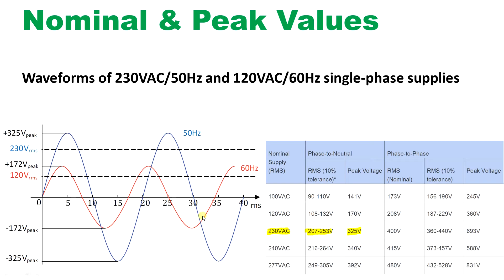If we see 230 volt 50 hertz, the 230 is the RMS value. This is very important information to remember: if you are checking with a multimeter, 230 volt is the RMS value. A 10% tolerance may be there, 207 to 253. And if you see the waveform, it follows a sine wave, and the peak value will be 325 volt. If it's a three-phase supply, the phase-to-phase value will be 400 volt, with a 10% tolerance of 360 to 440, and the peak voltage in that case will be 693.